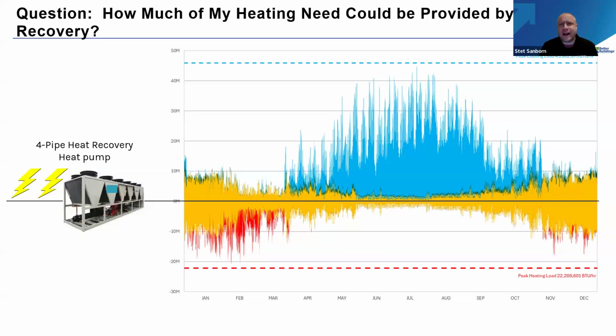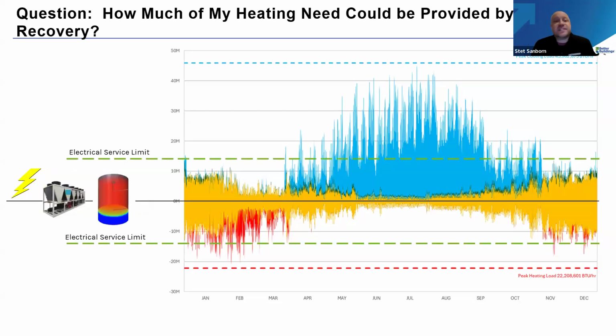There was a really great question in the Slido about houses of worship. I actually did a retrofit of a worship house that was trying to do a heat pump adoption, and their loads were not at all like a commercial office building. They all peaked on Sunday morning as they tried to warm up this massive sanctuary, and they had a massive boiler to do that, and it ran for 4 hours every week. Instead, we paired a small heat pump with a large storage tank and actually used that storage volume to meet that 4-hour peak load, and then used several days to recharge the tank. And so no electrical capacity upgrade required, and rather let that tank of water do the work for that short duration load.